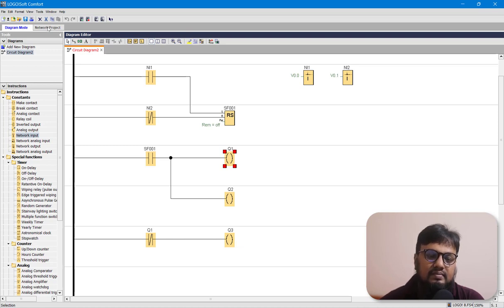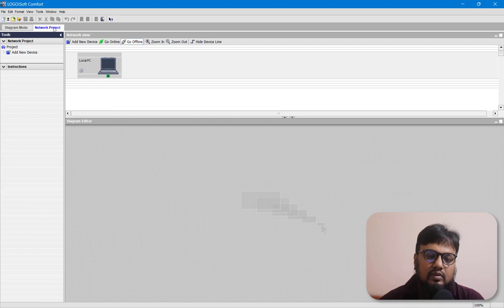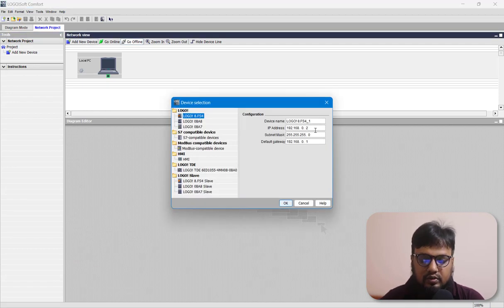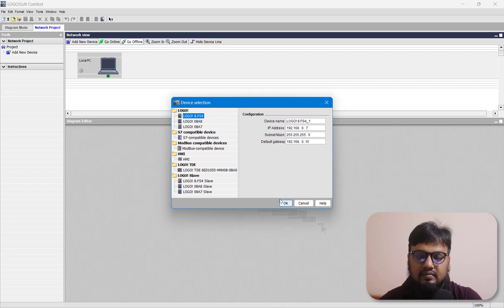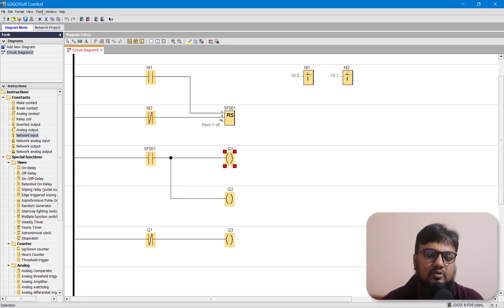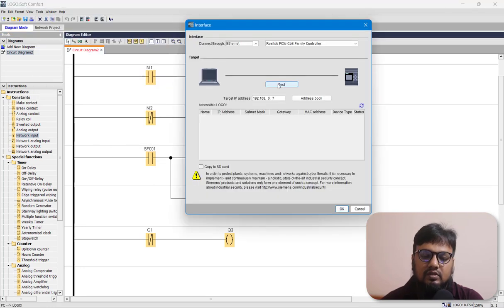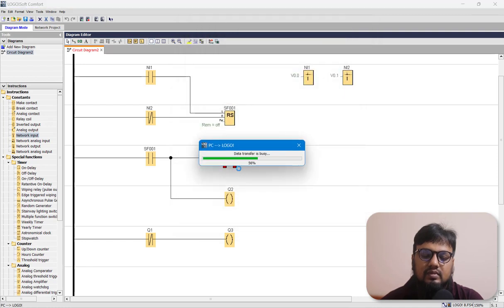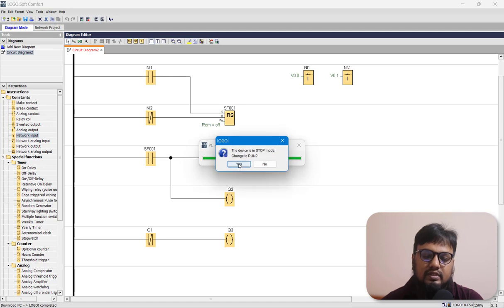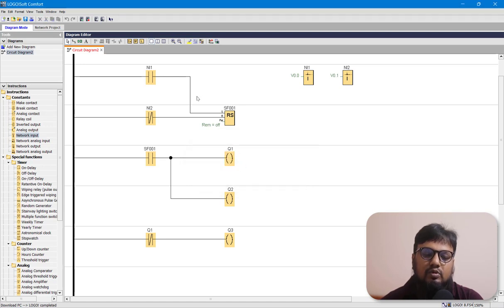Let's upload this program to our LOGO PLC. Go to the Network tab and put in your network addresses. Press OK, go back to Diagram mode, go to Tools, Transfer PC to LOGO, choose your Realtek driver, put in the correct IP address, and press OK. Your LOGO PLC must be connected to your PC using Ethernet for this operation.